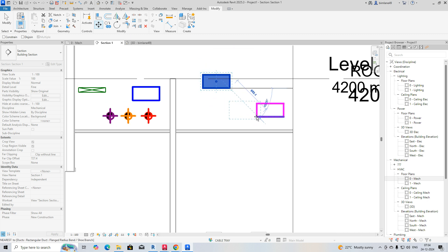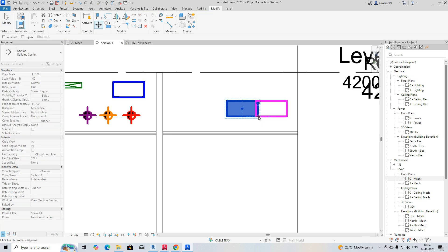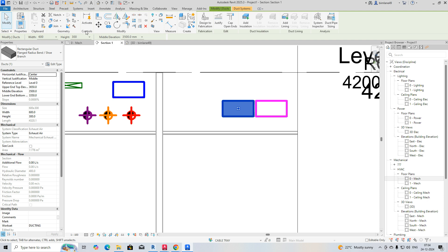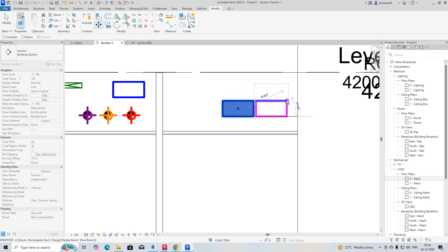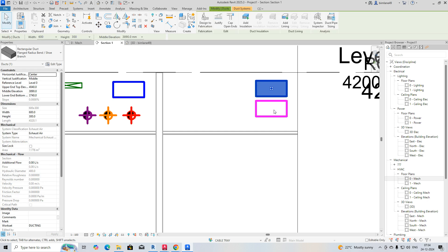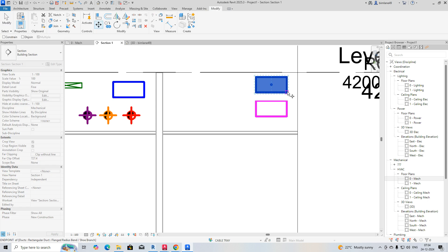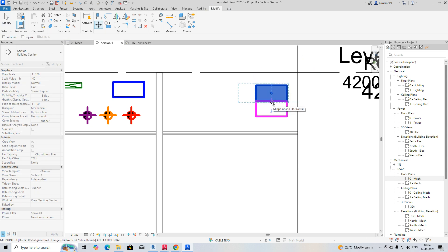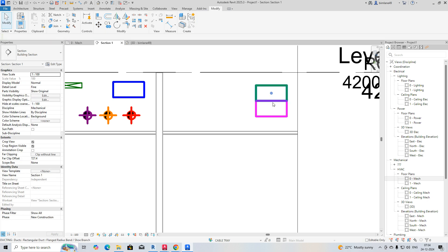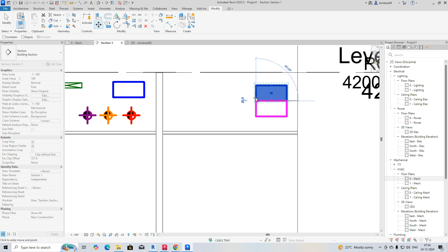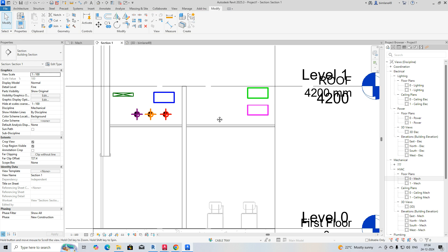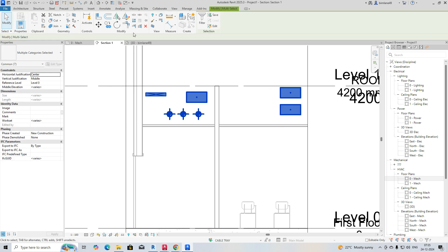Now this duct is going away from here — we can close this duct and move it like this. Even you can put it above this duct — some gap is required. If you have space, you can give 100mm, 150mm, or 200mm gap at least. So just put it here — with one support it will be going okay. Give 200mm from the top of this duct, so at 2200. You can arrange like this very easily.